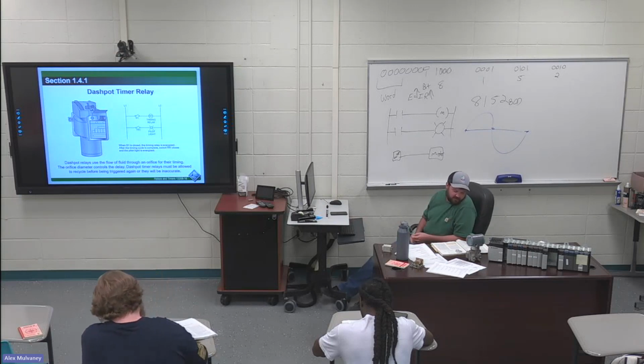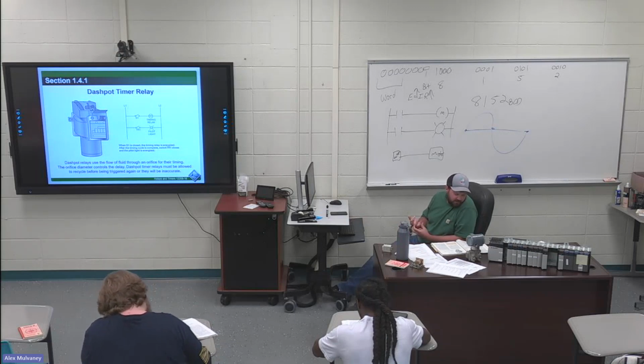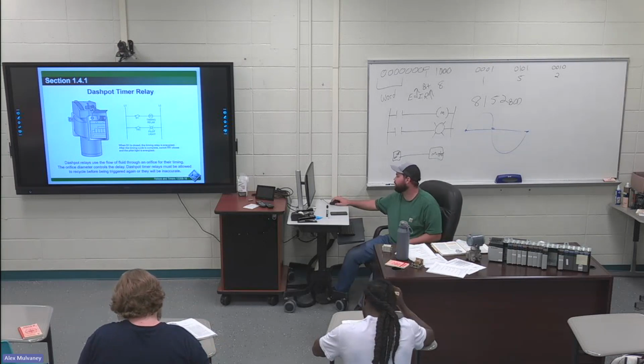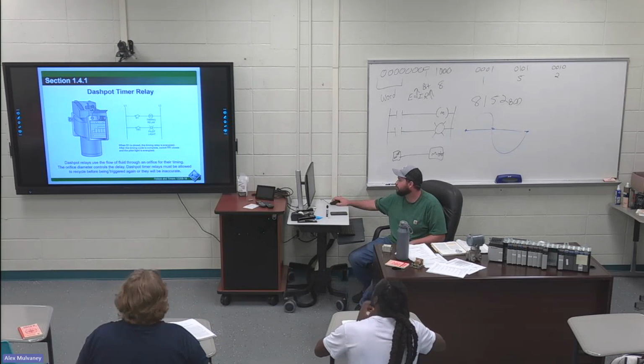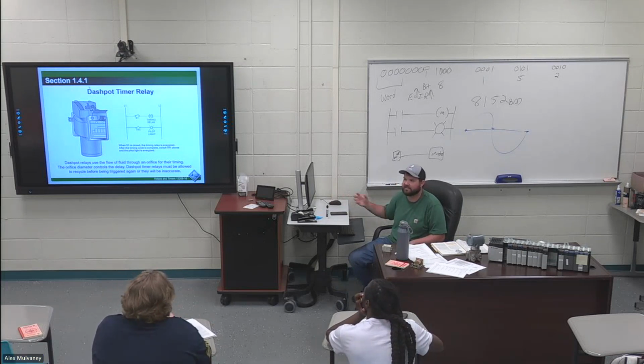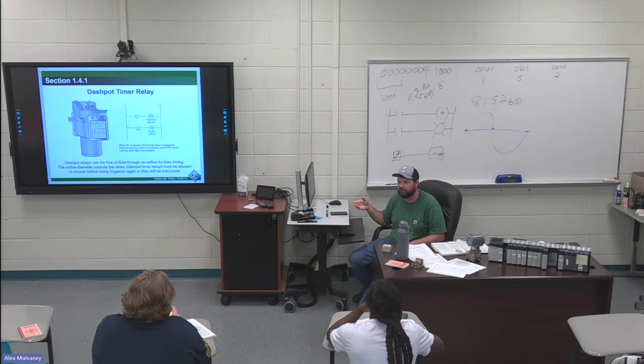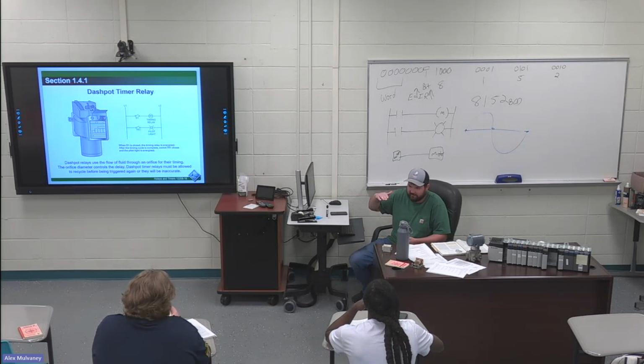(141) Dashpot timer relays. First sentence is highlighted. Magnetically operated oil dashpot timing relays may be used on voltages up to 600 volts AC. Essentially, what this does, it uses fluid flowing through an orifice. So you have a known viscosity fluid and you have a known orifice. It's essentially like a timer for a board game, except it's using oil, right? Like you flip a sand timer over, it takes a certain amount of time for that sand to get from the top to the bottom. This is the same, except it has electrical contacts on it, and it has an orifice and it uses oil instead of sand. Kind of the same thing.